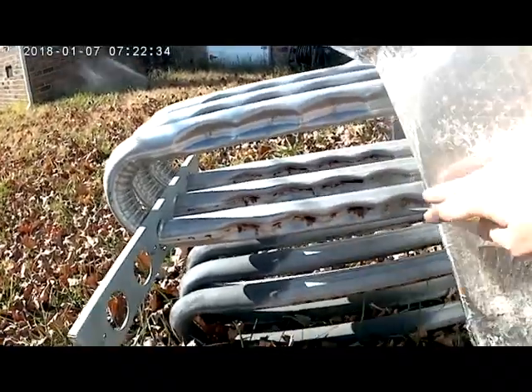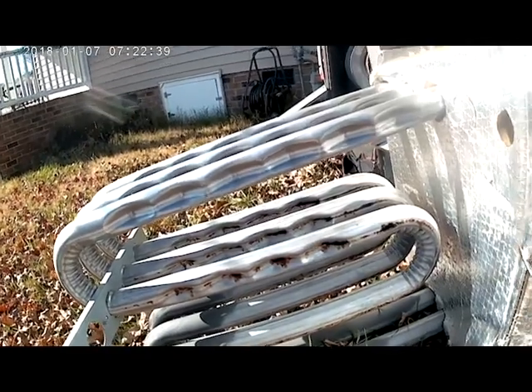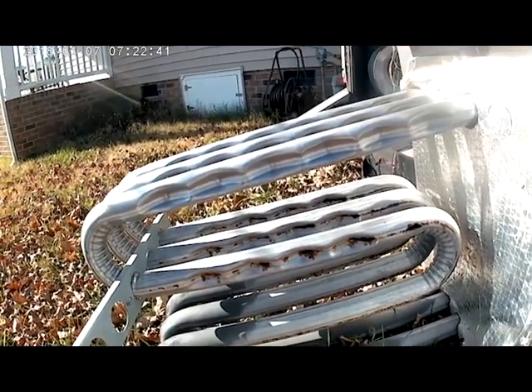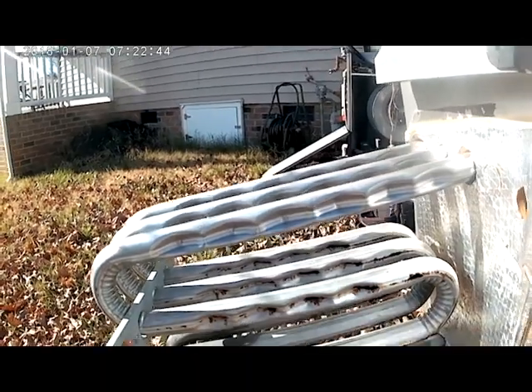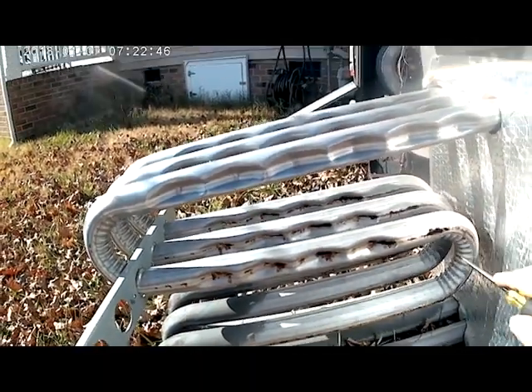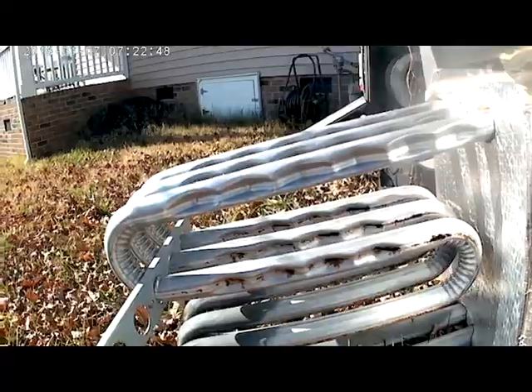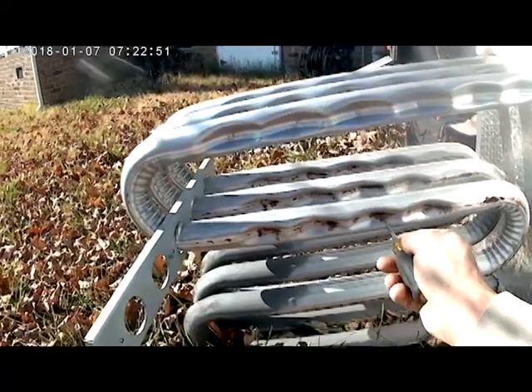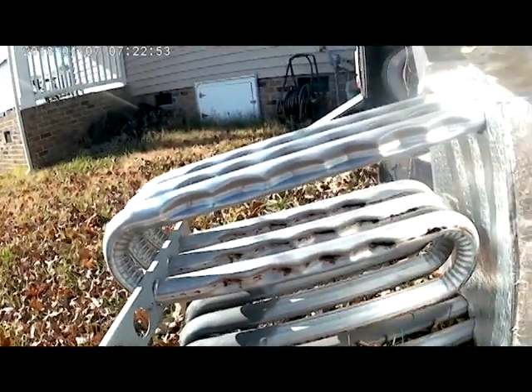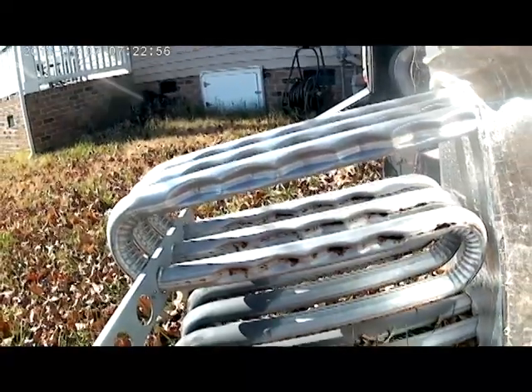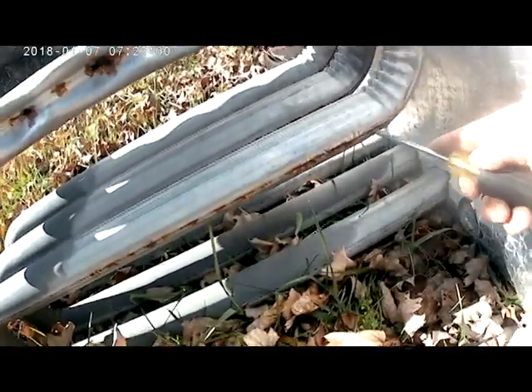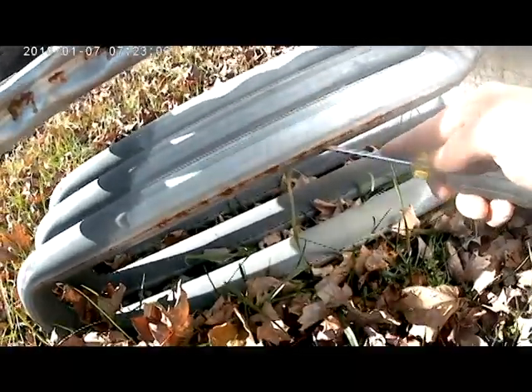That's the reason why. And when you start getting a crack like this, it'll start tripping your rollout switch to let you know there's a problem. This heat exchanger was in that cabinet, so it's really hard to check, but just always know when your rollout switch starts tripping, it signals that you're having a problem, and most of the time it's a heat exchanger problem. And you see, even down here on these seams, this thing is just rusted through.